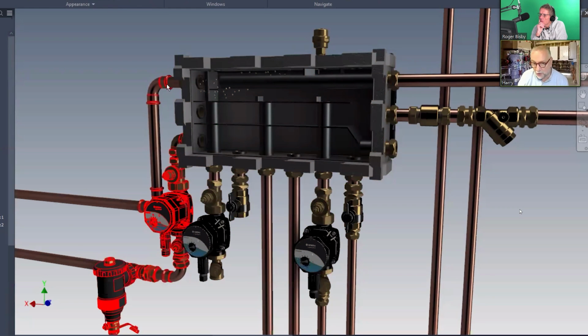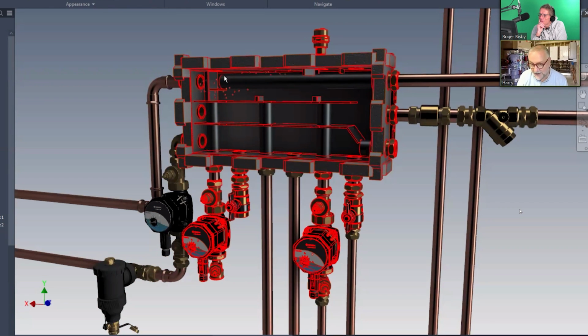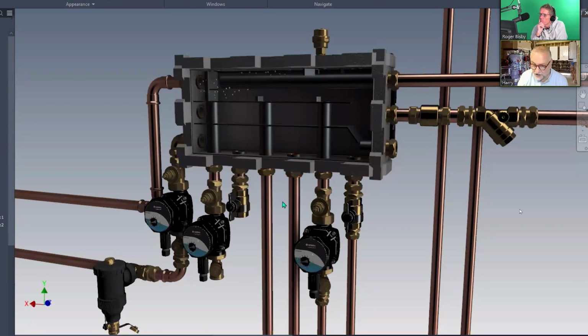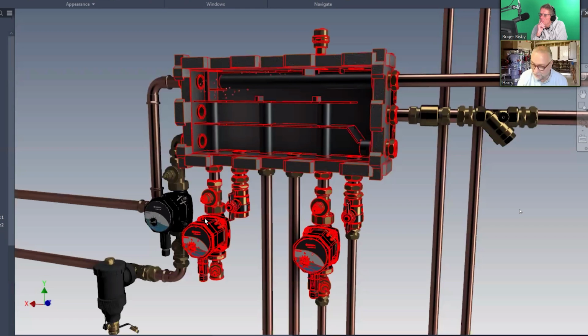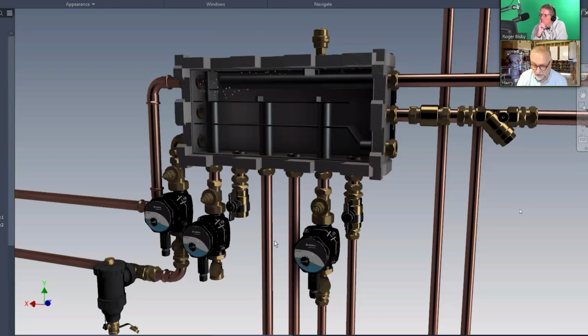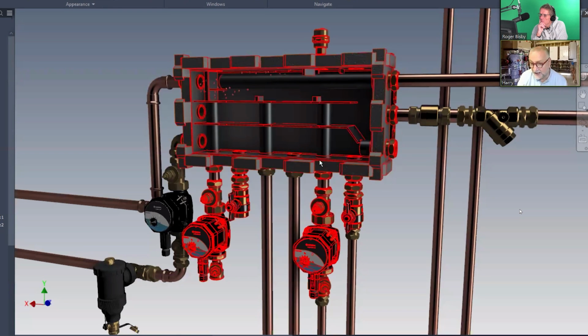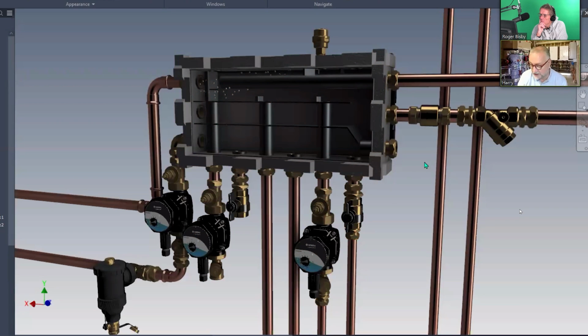Now the hottest water coming in from the heat pump is passing on the top chamber. It's passing these pipes that take heat away to zones. So if I turn on this pump, I might heat my hot water. If I turn this pump, I'll show you, there's a reason you wouldn't have a pump here. This would be underfloor heating. You don't need a pump on the manifold for underfloor heating. And this might be, say, a bedroom circuit heading up.